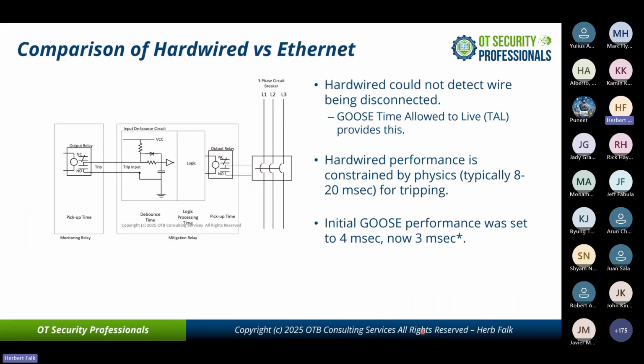Okay, so what are we doing in protection? On the left-hand side here is the hardware representation, where you have a coil and an output relay contacts that go into a trip input on an IED. And there's some logic here, and then an output. When we were doing the performance for the use case, they said 4 milliseconds. But if you look at the pickup time of these contacts versus the debounce time of the trip input, hardware performance is constrained by physics, and it's typically 8 to 20 milliseconds.